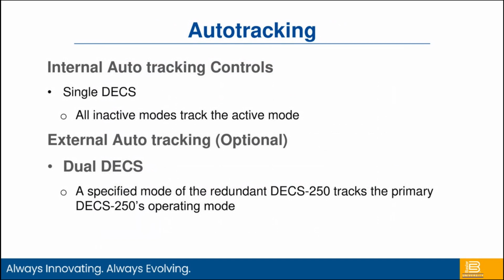But sometimes we need more redundancy than that. So we can add dual systems. We can add a whole second DECS. This is what we call external auto-tracking, which allows DECS to DECS communication. So we have a primary DECS, which is actually doing the work, and then we have the backup DECS, which through communications is monitoring what the primary DECS is doing. In the case of a fault with that primary DECS, I can transfer to my secondary DECS, again keeping that machine online until I have a regular maintenance cycle or need to take it down for other reasons.